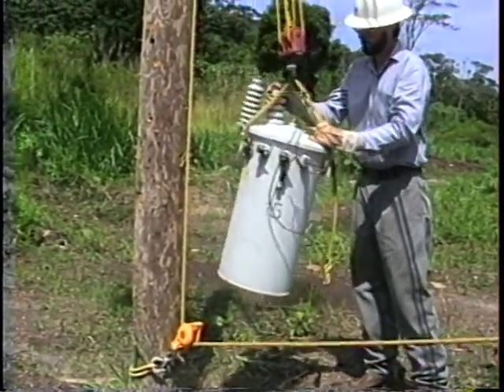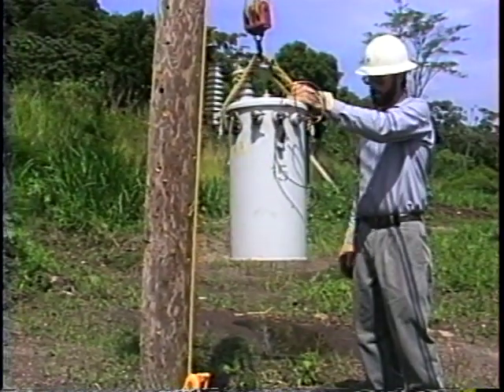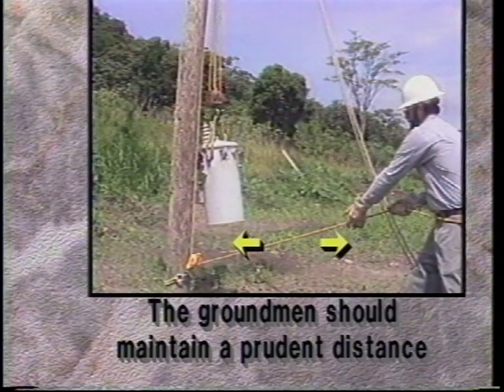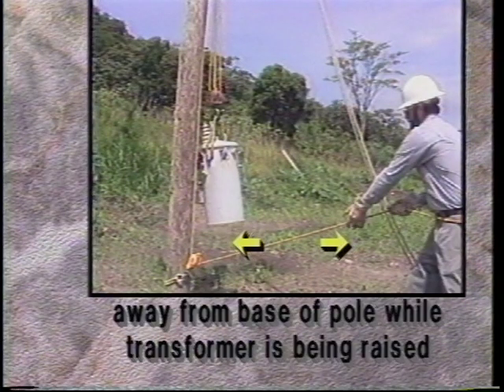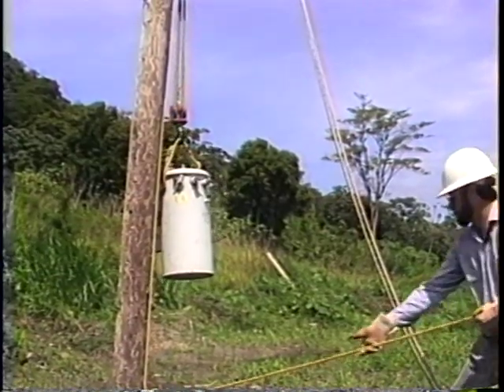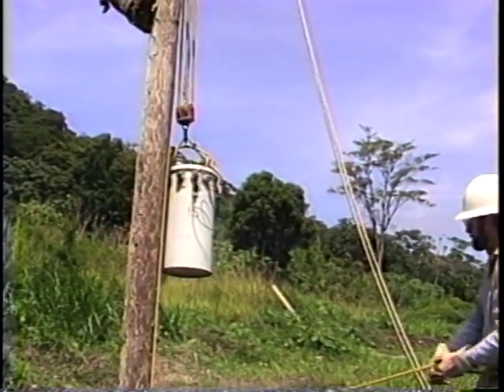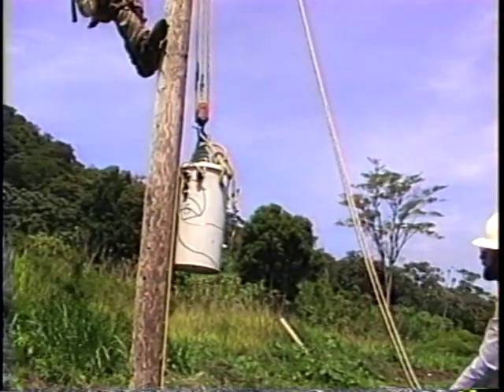In certain situations, such as when obstacles are present on the pole, the transformer has a third attachment point on the bottom of the tank where a control rope can be attached. This rope can be used to help guide and balance the transformer while it is being raised. The groundman should maintain a prudent distance away from the base of the pole while the transformer is being raised. When the groundmen receive the order to raise the transformer, they should do so in a smooth, even manner.